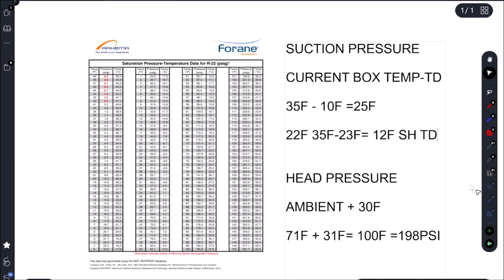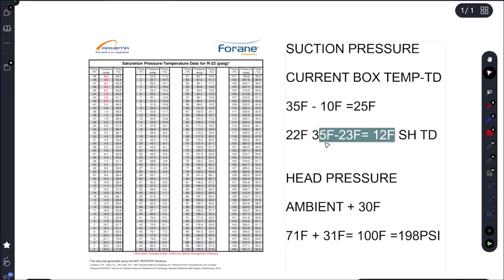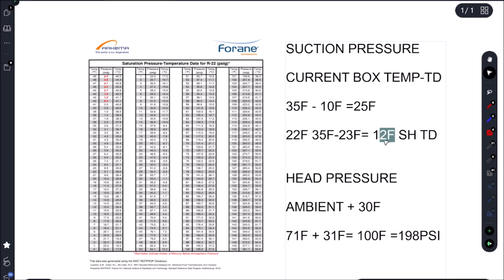But we're at a 12 Fahrenheit superheat or 12 Fahrenheit TD approximately. I want it to be 10. I'm not going to mess around with this valve, especially if I can't take my suction pressure right at the coil. So we're going to live with our 12 Fahrenheit TD. The box is cooling really well. In any other case in the other videos you see I like to adjust this to somewhere around 8 to 10 superheat on these walk-in coolers. This thing's super old. We're going to have efficiency issues regardless. The customer didn't want to put a new system in, they were quoted that. This repair was probably 25 percent of putting in a new system. So they went with the repair.